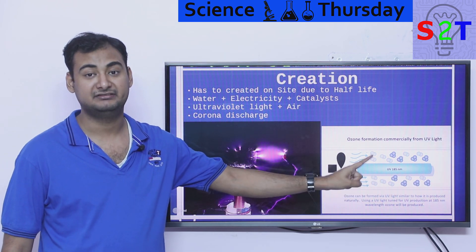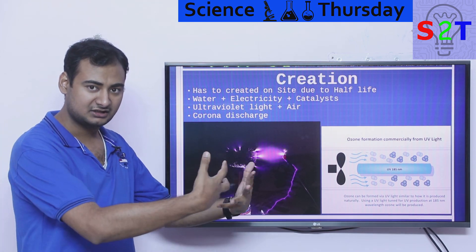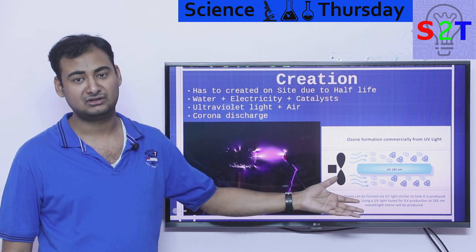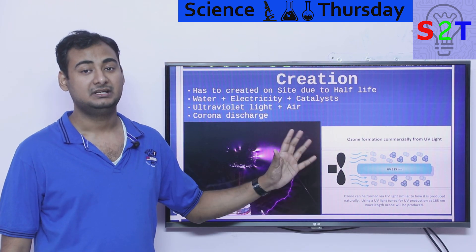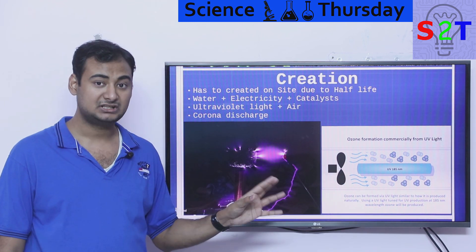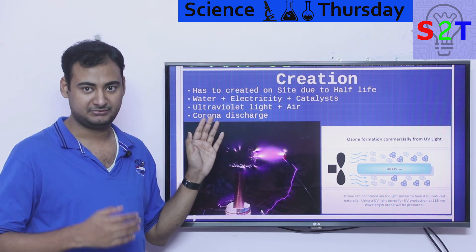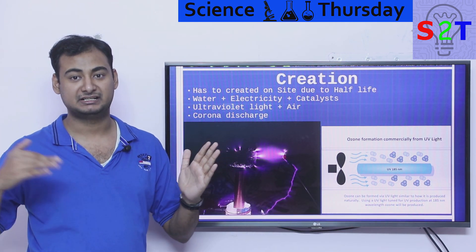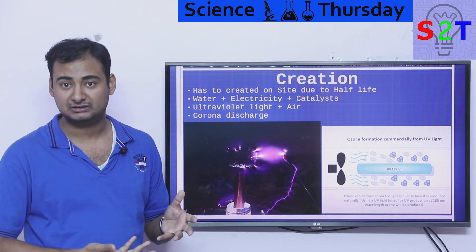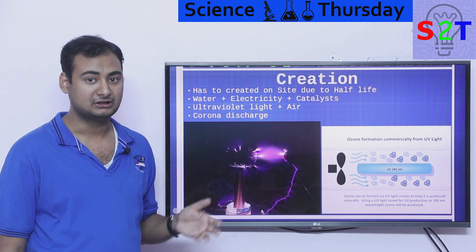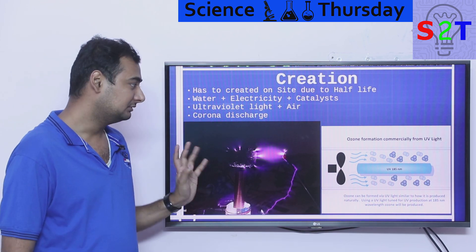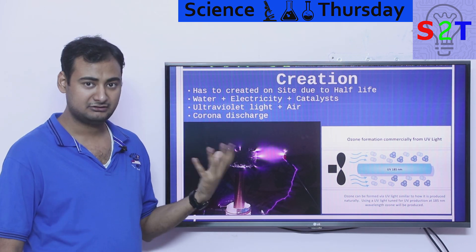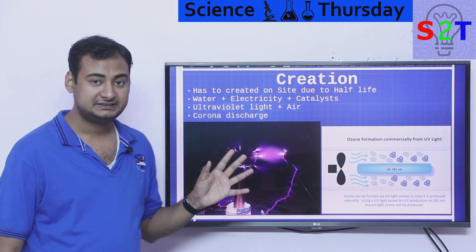Another method mimics how ozone is naturally created: you use a UV lamp at 185 nanometers and run normal air through it, which converts some of the air into O3. This produces lower concentrations but is efficient and creates no byproducts. A third method is corona discharge — using high voltage to create lightning-like sparks between electrodes, similar to what happens naturally during lightning strikes. In a water treatment plant you may use UV lamps or a larger-scale electrolysis or corona discharge system. All of these are energy intensive.